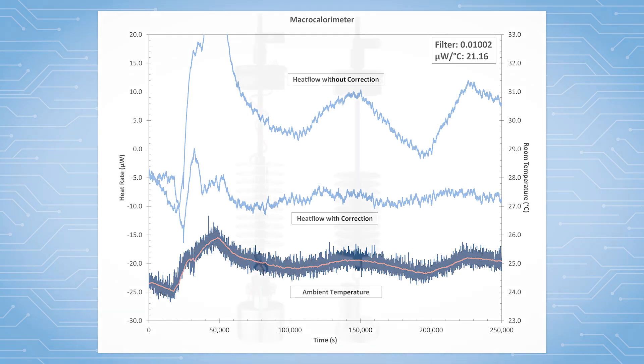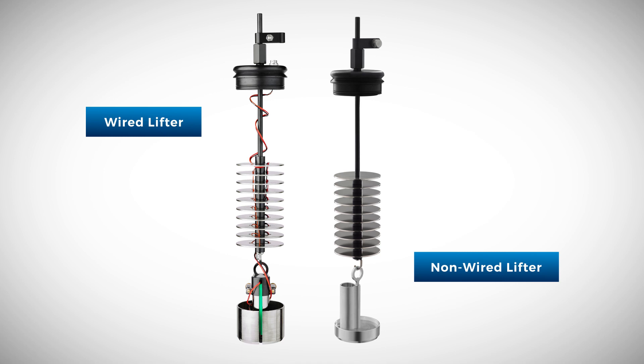It is important to note that different configurations, for example, wired versus non-wired might have different time constants and heat flow dependencies associated with them. So it is advised to repeat this procedure for each configuration and adjust the values in TAM Assistant prior to collecting data.